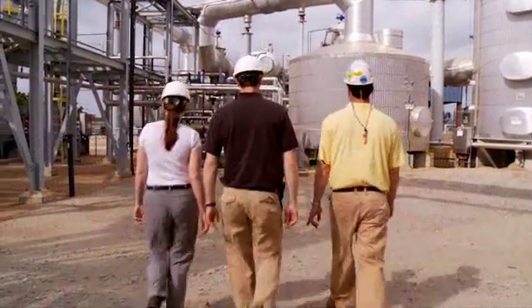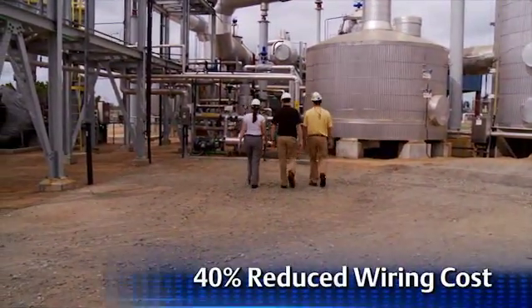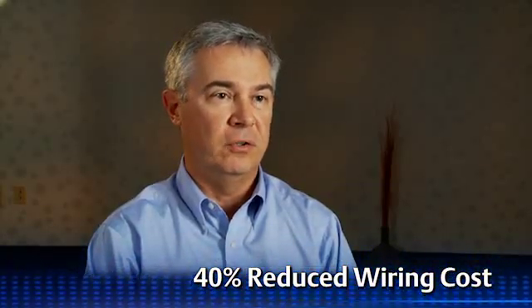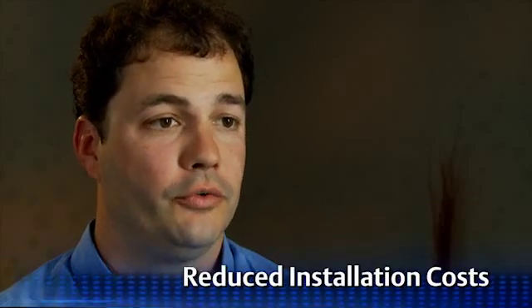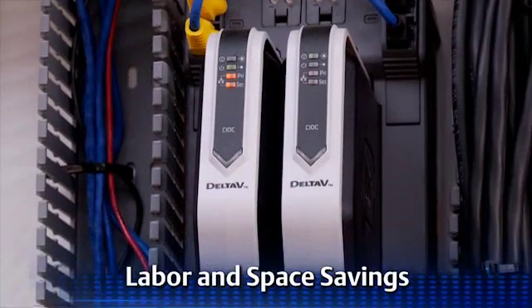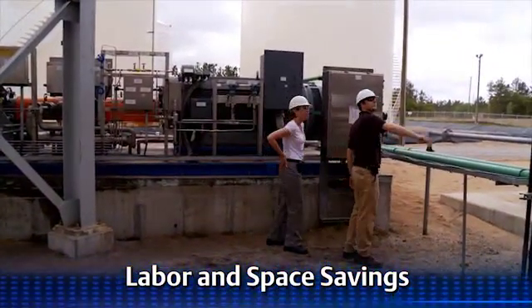The primary savings for this choice was the construction costs, and with the CHARM system, the savings were probably about 40% over a traditional wired system. Utilizing the CHARM I/O structure, you're able to reduce the amount of wiring in the field, reduce the labor cost associated with running those wires, and increase the start-up time of your plant, and of course, deliver product faster. The traditional marshaling cabinets were eliminated. Basically, we come from the CHARM modules with dual Ethernet cabling into the control room.